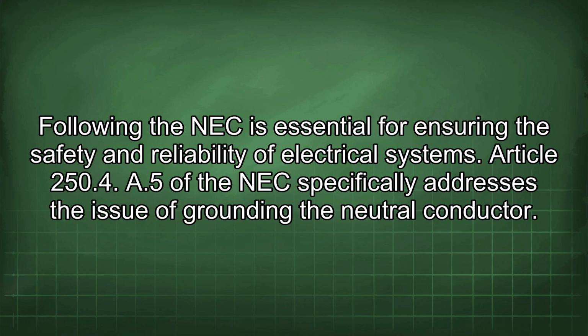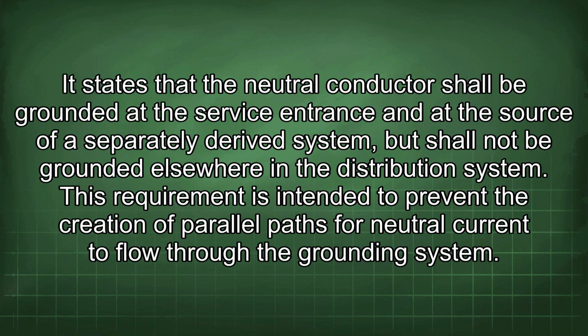A5 of the NEC specifically addresses the issue of grounding the neutral conductor. It states that the neutral conductor shall be grounded at the service entrance and at the source of a separately derived system, but shall not be grounded elsewhere in the distribution system. This requirement is intended to prevent the creation of parallel paths for neutral current to flow through the grounding system.